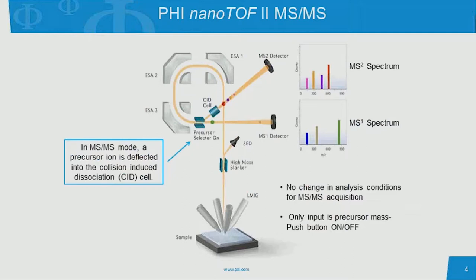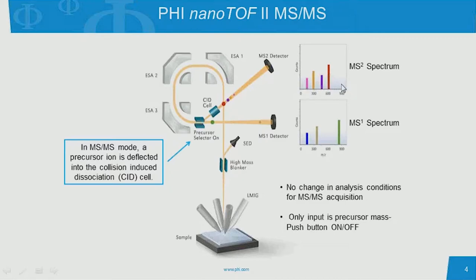So how did we implement that? Here's a schematic of the Phi-nano-TOF-2. The primary ion is pulsed down to the sample surface; TOF-SIMS secondary ions go around three ESAs to the MS-1 detector, and here's where we record our TOF-SIMS spectrum. If there's a specific peak in that spectrum that you want to identify, we've added a precursor selector after the third ESA, which deflects the ion up into the collision-induced dissociation cell where it's fragmented. After going through the collision cell, which is filled with argon, it fragments into characteristic fragments from that precursor, and we record the MS-2 spectrum — the MS-MS or tandem MS spectrum of that one particular mass.